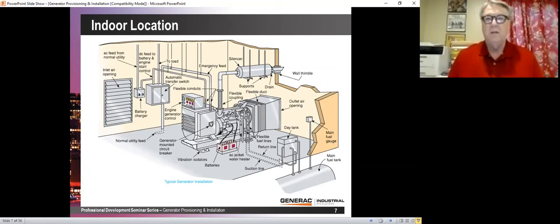First of all, let's look at the conduit and attachments to the generator. Generators vibrate, so anything that's attached to the generator has to have a flex coupling. Well, here's our sheet metal going to the exhaust louver. That's got a flex duct on it. Your silencer has a flex coupling. It shows the conduits here have flex couplings, flexible fuel lines to the day tank, and flexible to the battery. So that looks pretty good to me, and I think they did a good job, and the artist let you know that that's important. How about those batteries?